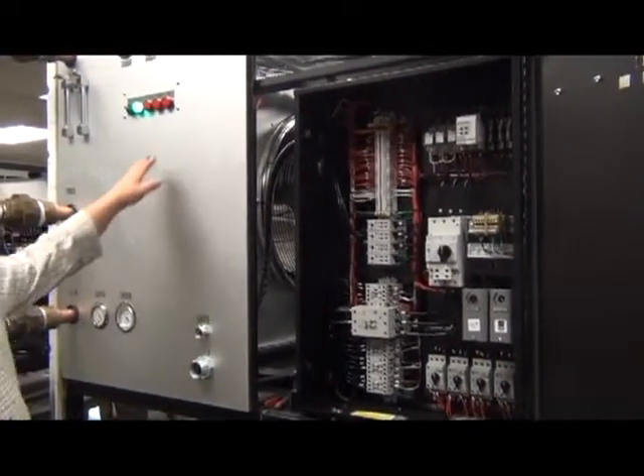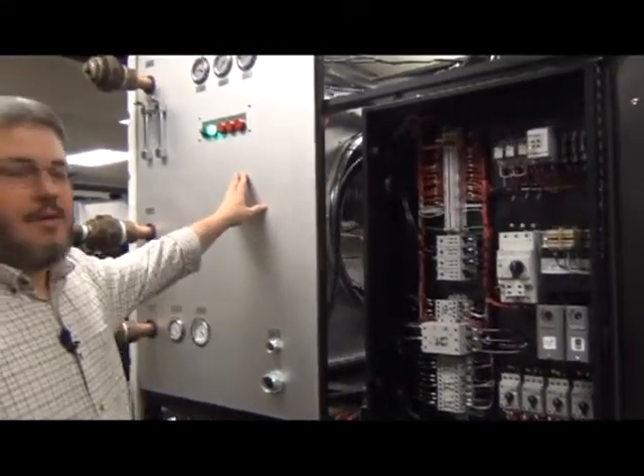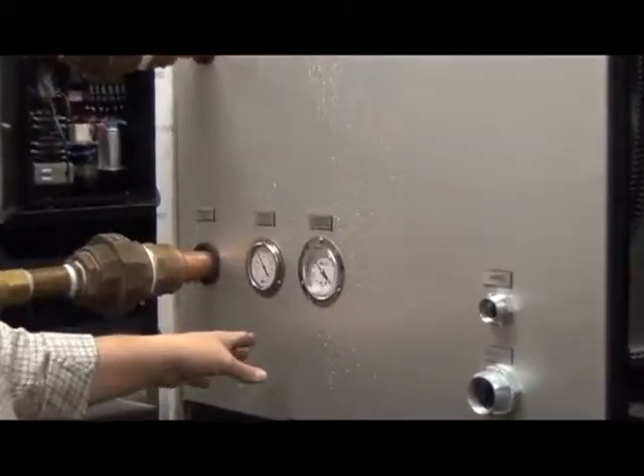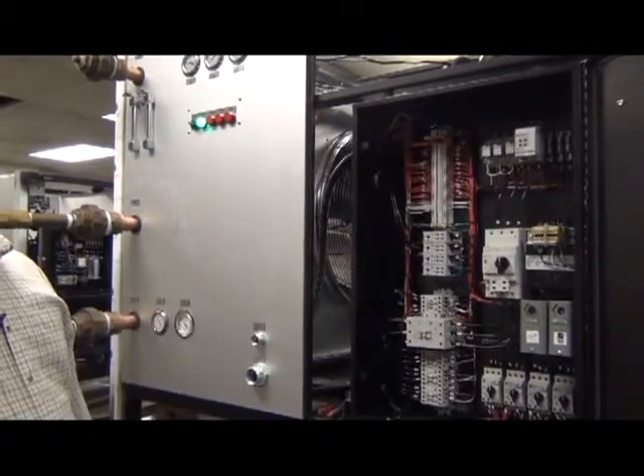The pump is designed to run continuously. And you'll just want to make sure that in the field you set up your flow rate and your pressure for what it's supposed to be set to, in this case 35 gallons a minute at 65 PSI.